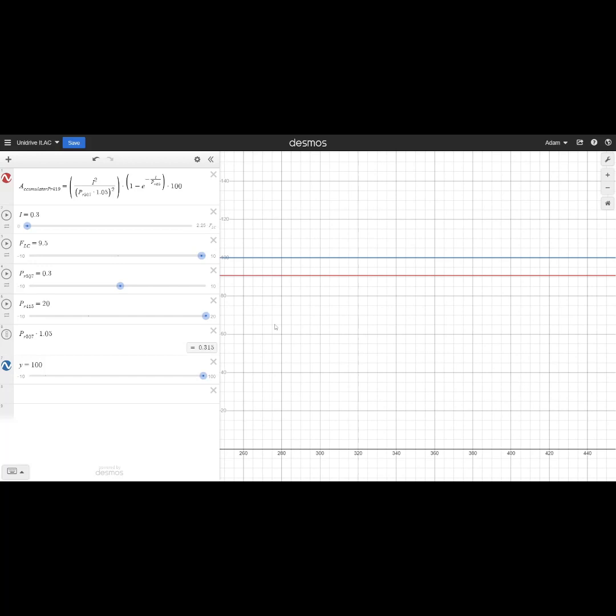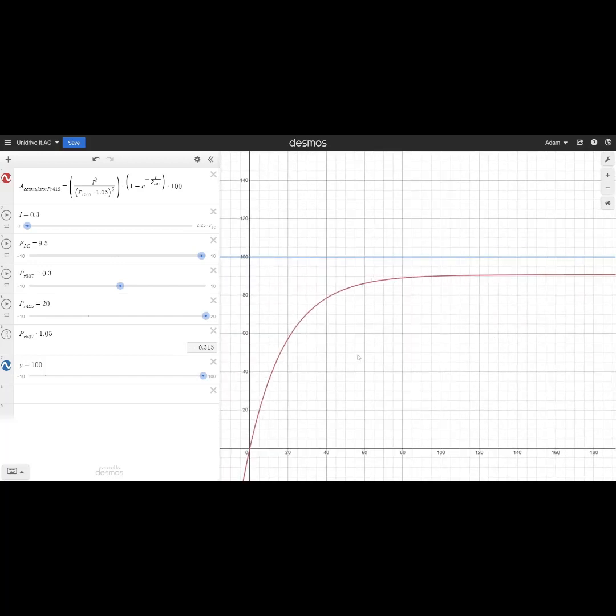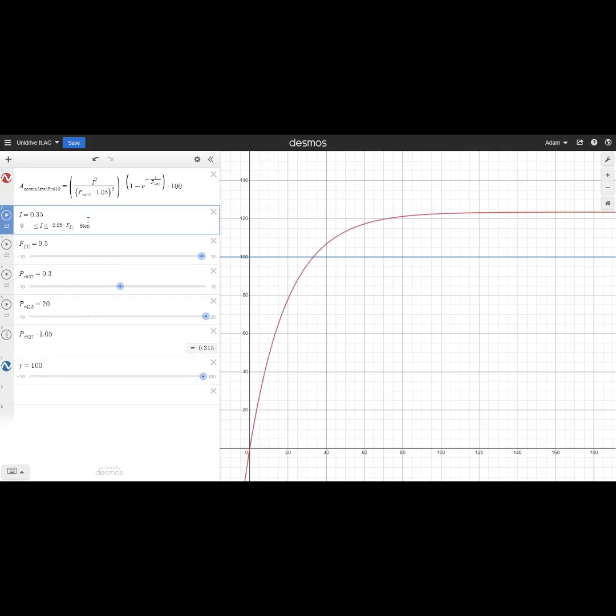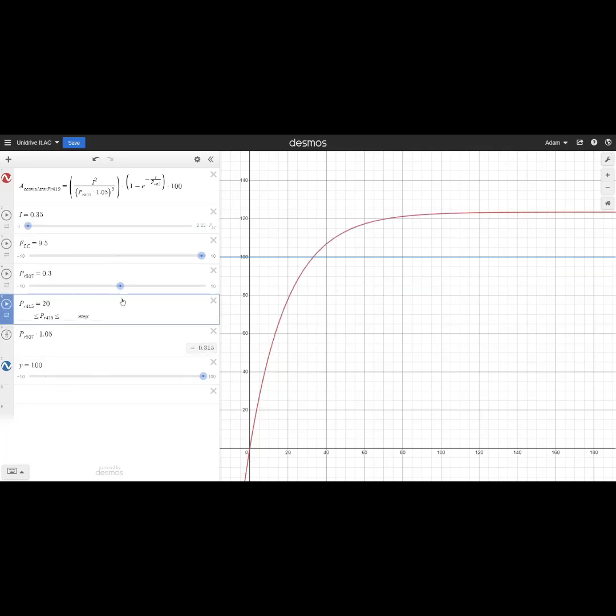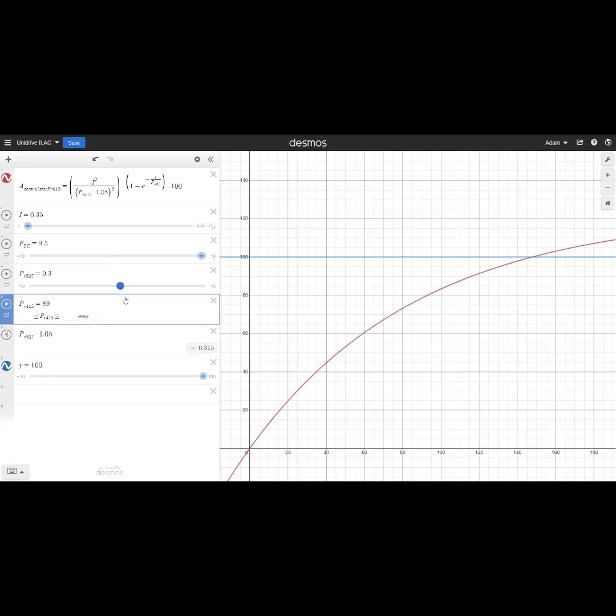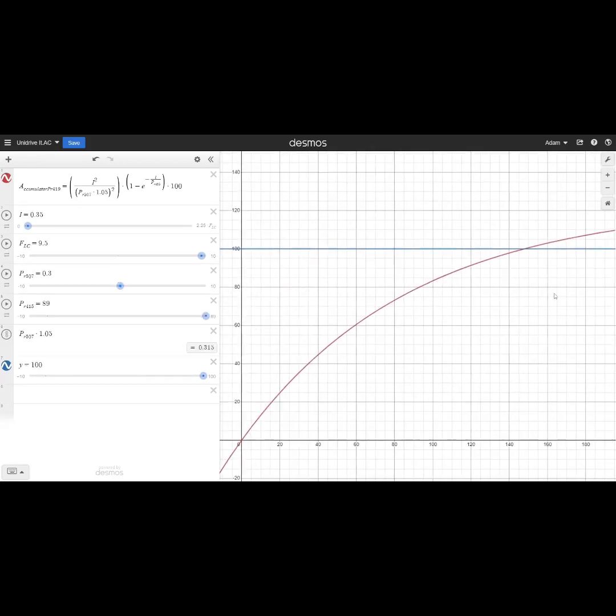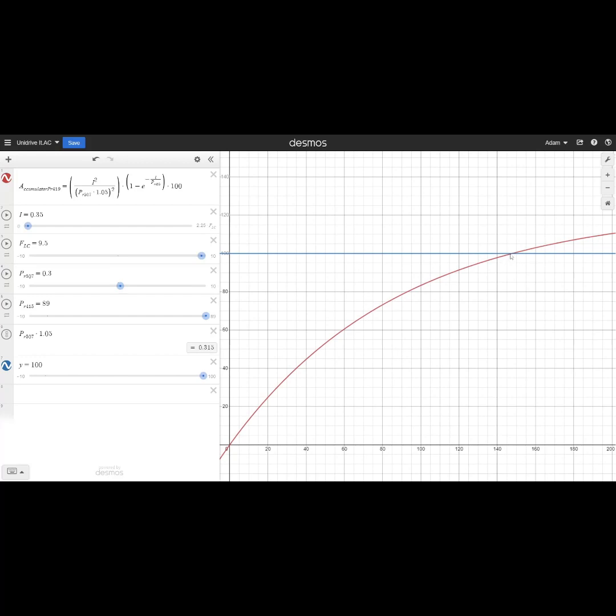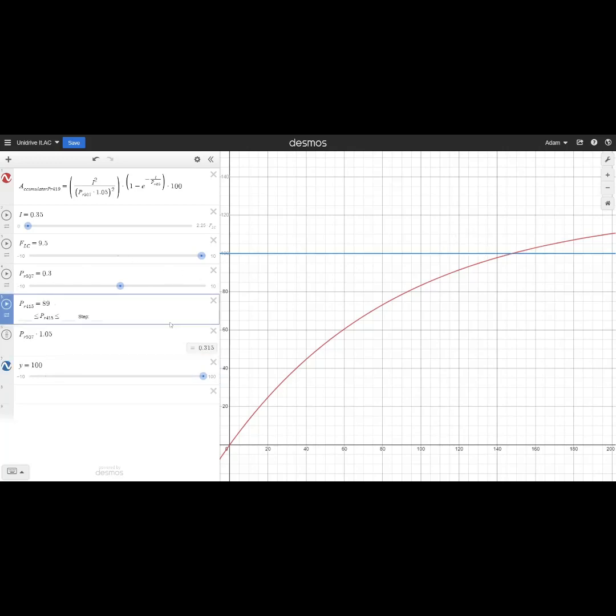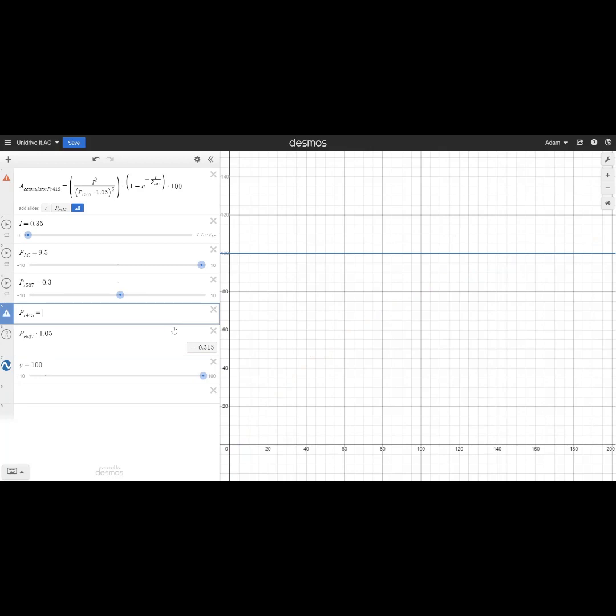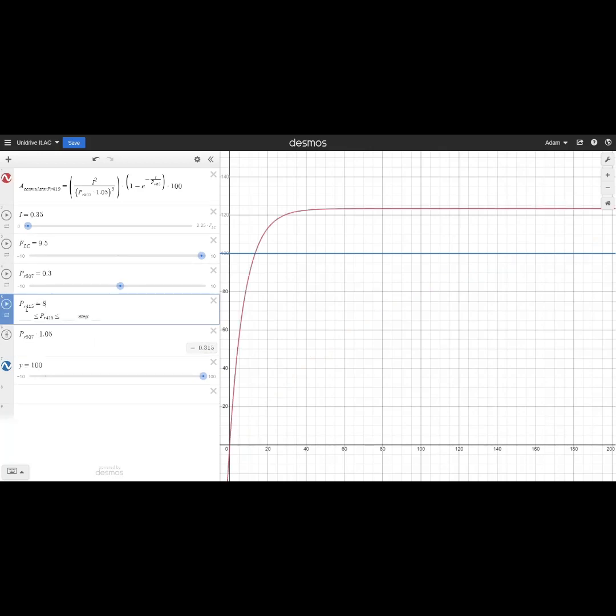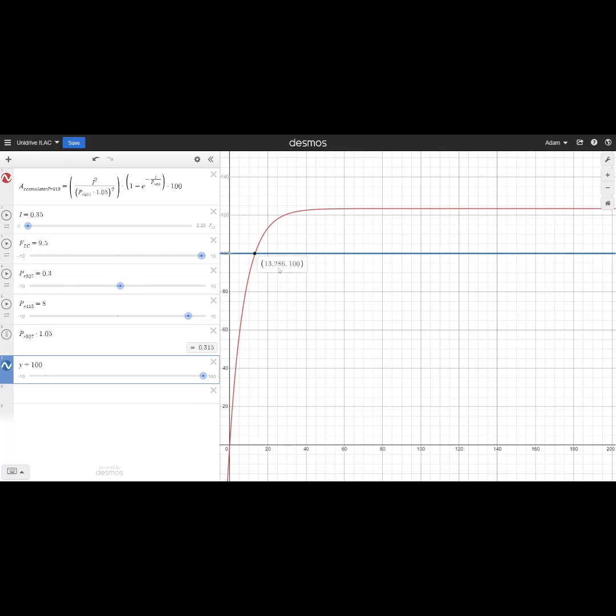This shows a drive operating under normal conditions that won't trip out to an ITAC. Now, if I increase the current back up to where the drive will trip and increase my time base — let's say 89, which would be the default value for an induction motor — the trip point increases to 147 seconds. So we can increase and decrease the time it takes for the drive to trip by changing the value of parameter 415, that time base. If we lower it, the drive should trip in only 13 seconds.